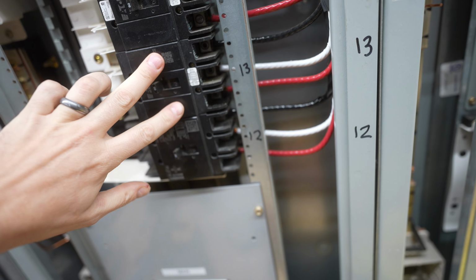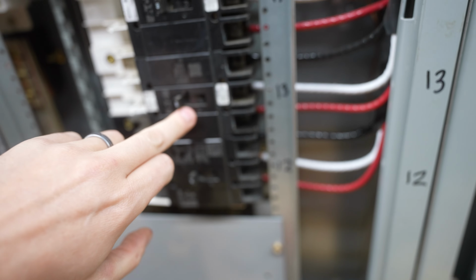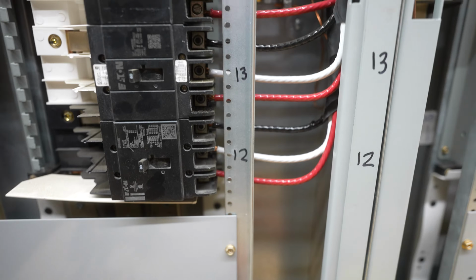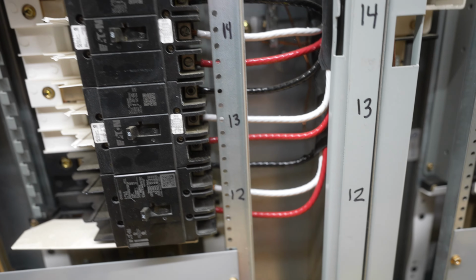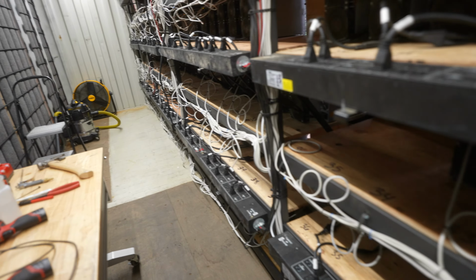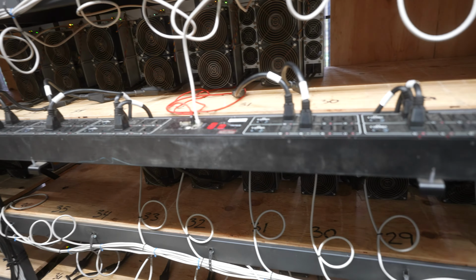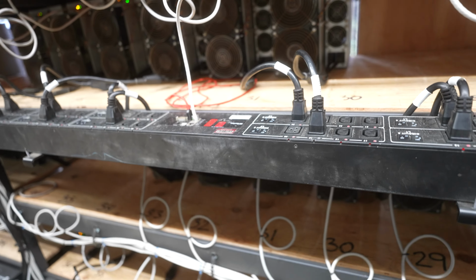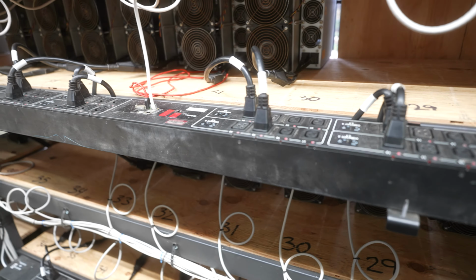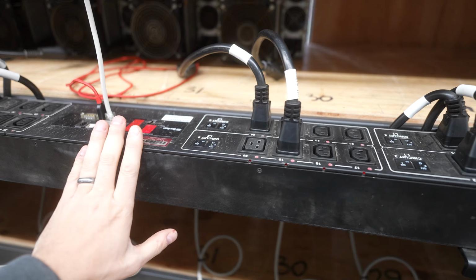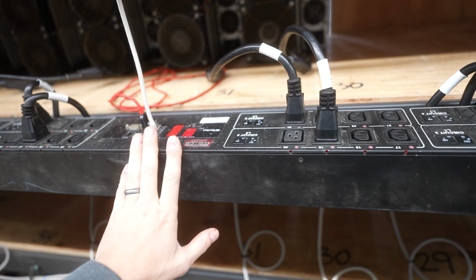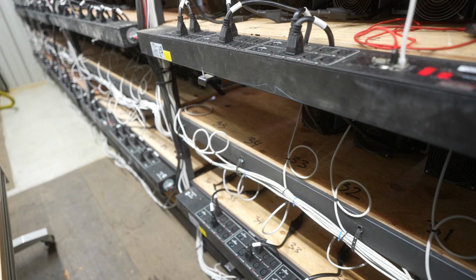So this is number 13 - we can come back here and match it up. This is the exact PDU, so we can measure these three and we'll have the exact amperage using this tool. We don't really need to do that though, because these are smart PDUs - we can just log into the IP address of this PDU and we'll know the exact load. But when you want to match it up and see that the PDU is reporting properly, you could check it here.